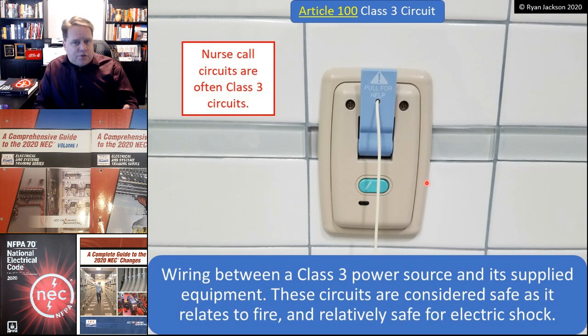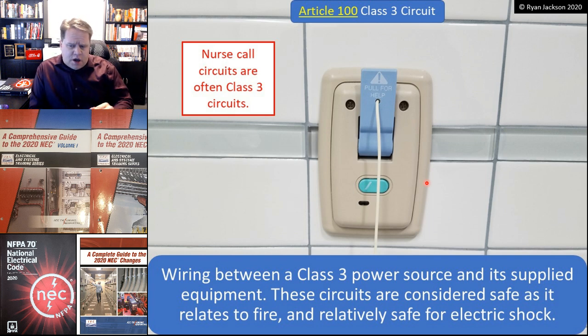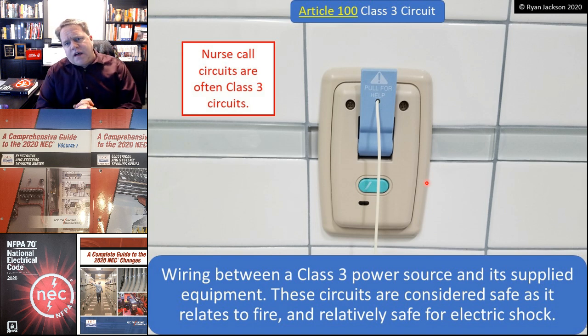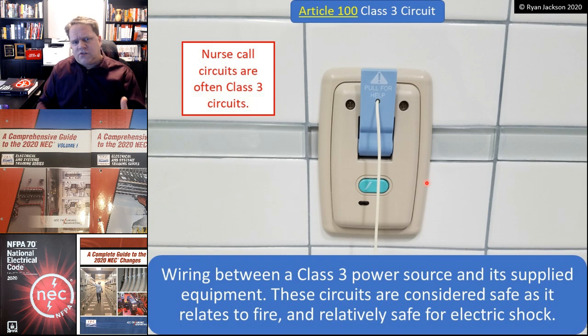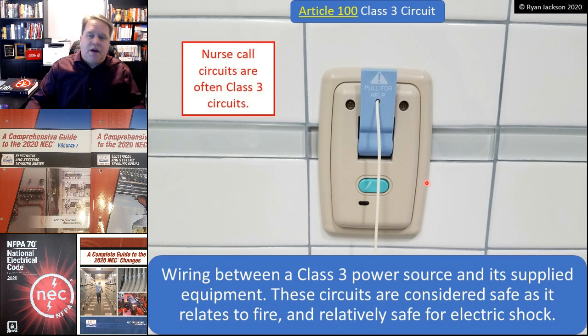Similarly, a class 3 circuit is the wiring between a class 3 power source and its supplied equipment. These circuits are considered safe as it relates to fire, and safe enough as it relates to electric shock. We can get higher voltages with class 3 circuits, so we don't have quite the same shock safety as class 2. However, by limiting voltage and current, a class 3 circuit is considered safe from fire and safe enough from shock. A common example of a class 3 circuit would be a nurse call system, though most limited-energy circuits are typically class 2.